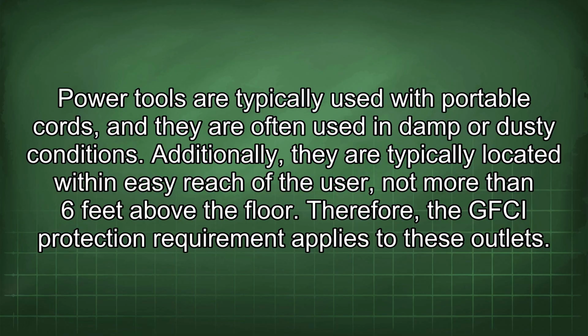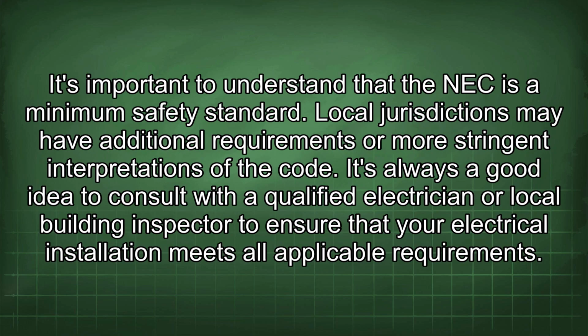Additionally, they are typically located within easy reach of the user, not more than 6 feet above the floor. Therefore, the GFCI protection requirement applies to these outlets. It's important to understand that the NEC is a minimum safety standard. Local jurisdictions may have additional requirements or more stringent interpretations of the code. It's always a good idea to consult with a qualified electrician or local building inspector to ensure that your electrical installation meets all applicable requirements.